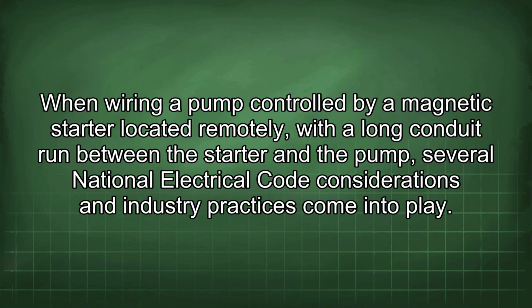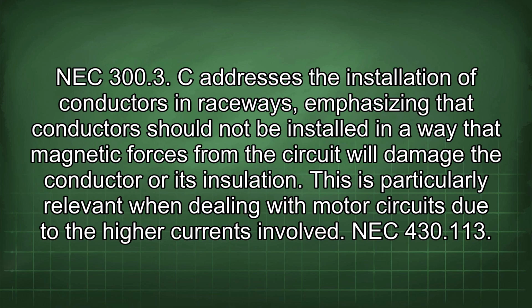When wiring a pump controlled by a magnetic starter located remotely with a long conduit run between the starter and the pump, several National Electrical Code considerations and industry practices come into play. NEC 300.3(C) addresses the installation of conductors in raceways, emphasizing that conductors should not be installed in a way that magnetic forces from the circuit will damage the conductor or its insulation. This is particularly relevant when dealing with motor circuits due to the higher currents involved.